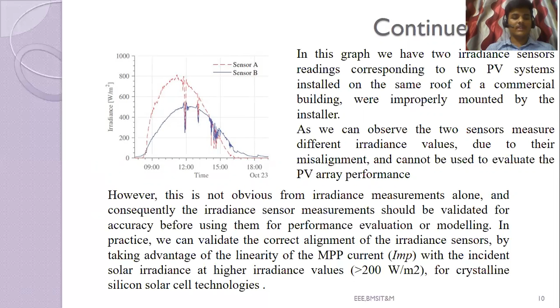In practice, we can validate the correct alignment of irradiance sensors by taking advantage of the linearity of the MPP current with the incident solar irradiance at higher irradiance values for crystalline silicon solar cell technologies. As we see in the graph, we have plots of two sensors, sensor A and sensor B, of two different PV systems installed on the same roof of a commercial building. For sensor A, we see an abrupt rise in the irradiance with respect to time. Sensor B is entirely different from sensor A, due to the misalignment of one PV system, that is sensor A. This abrupt rise in irradiance cannot be taken into consideration while validating or checking the PV array performance.